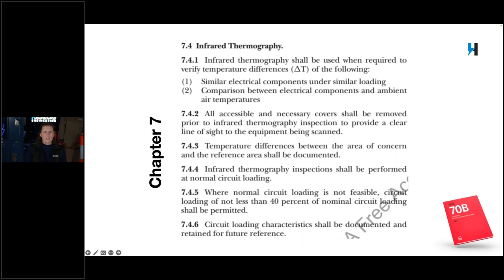There are other considerations too. If you're comparing two breakers in the same panel, but one has only a couple outlets and the other has a whole bunch of stuff running off it, that one has more load and demand and will potentially run hotter. So we have to think about similar electrical loads as well.